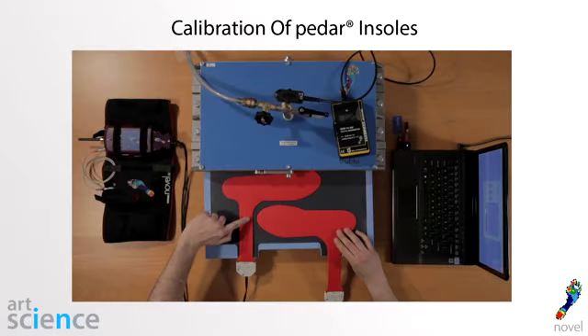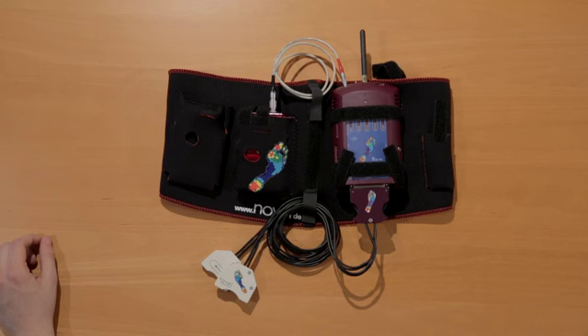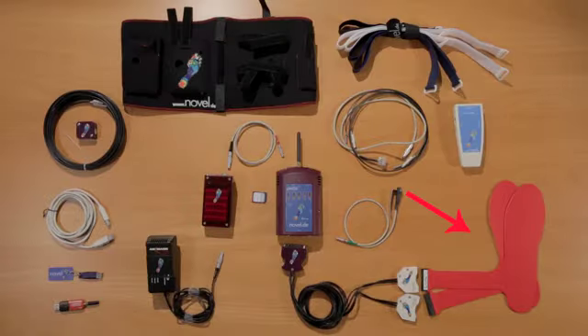Pedar calibration, Section 3. Step 1. The pedar calibration process uses the pedar box and insoles for a real-time, online calibration. Therefore, we use the insoles, insole cable, pedar box, battery cable, and battery in order to complete the calibration process.